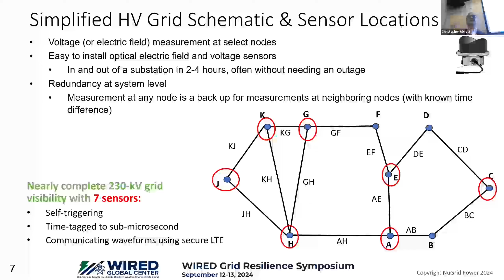It's a tool. The important thing about it is to be deployable. More important is to work all the time. The way it's designed, because you use the voltage traveling wave as opposed to current, where most relays work, if any one of these sensors is not available, the wave still travels to the next substation. That is a backup—grid-level redundancy. You don't have to double every device; you use the neighboring device. It may not be as perfect, maybe not within the tower, maybe a tower and a half, which for all practical purposes is the same location. But that's a tool that helps locate the fault.